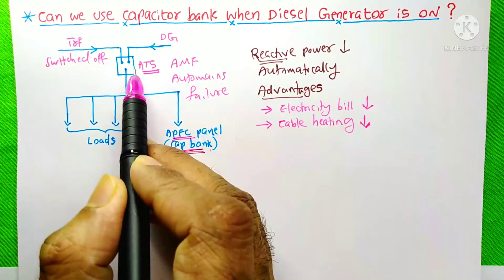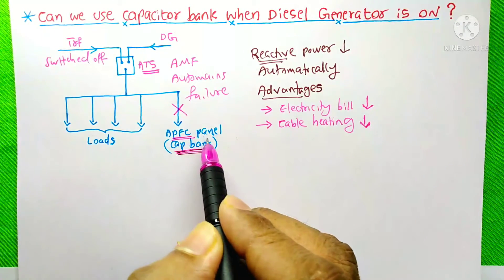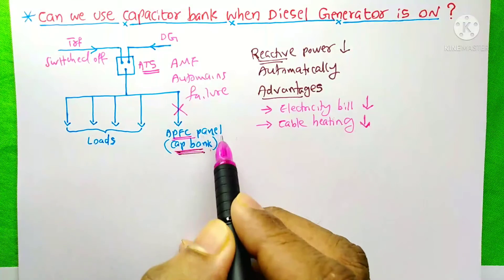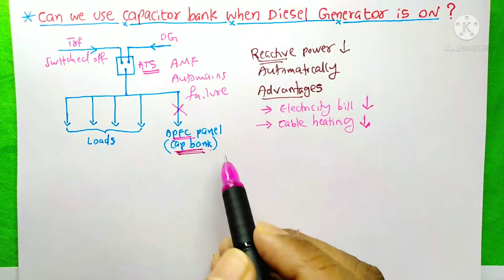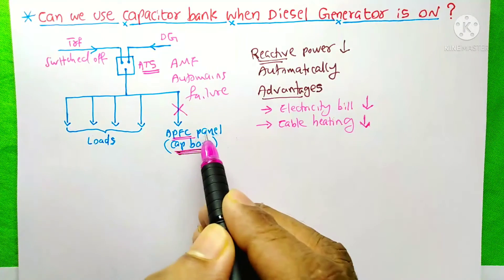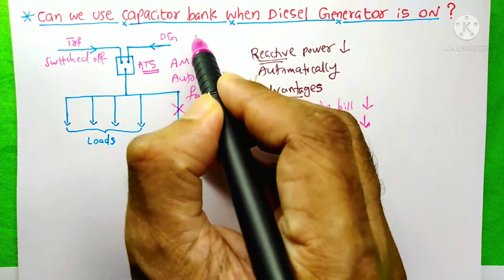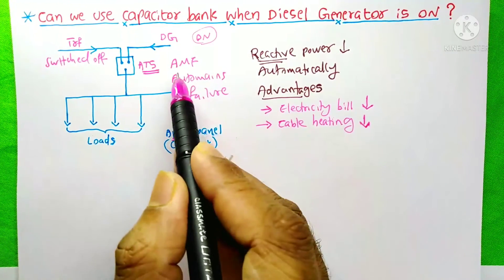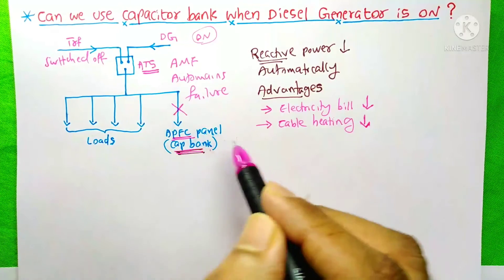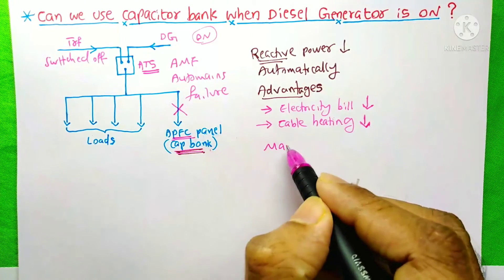But before that, we need to switch off this APFC panel circuit breaker — and this is also done automatically. The provision should be made to switch off this APFC panel before the DG is switched on. This AMF relay handles it automatically, but in some cases some buildings have only a manual changeover switch.